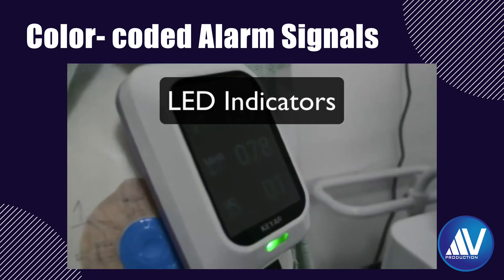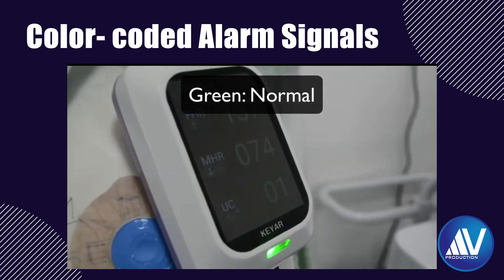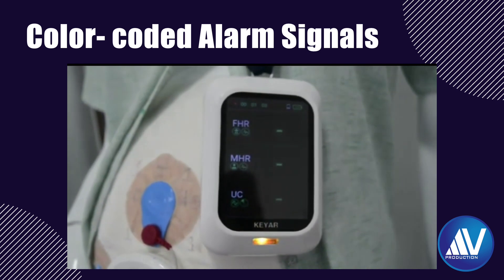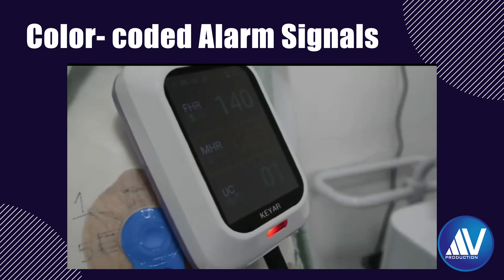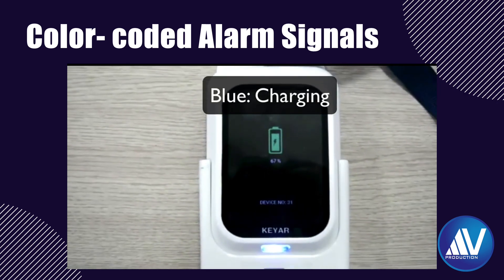One feature I like is the color-coded alarm signals emitted by the KEYAR device. If the LED shows green with uniform beams, the condition of the fetus and mother is normal. Orange color means there is a disconnection — you will need to reconnect the device. Red color with a high-pitched beeping sound indicates a critical condition: fetal or maternal tachycardia or bradycardia. In this situation, staff should immediately inform the obstetrician. Blue light indicates the device is being charged when placed in the charging dock.